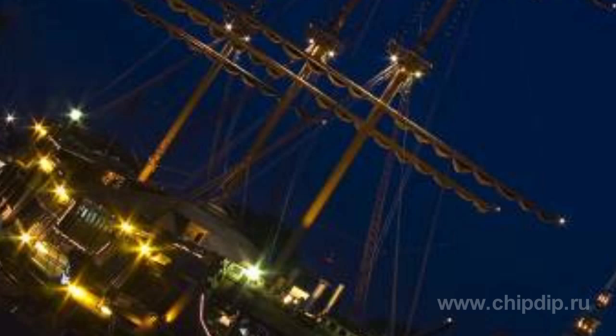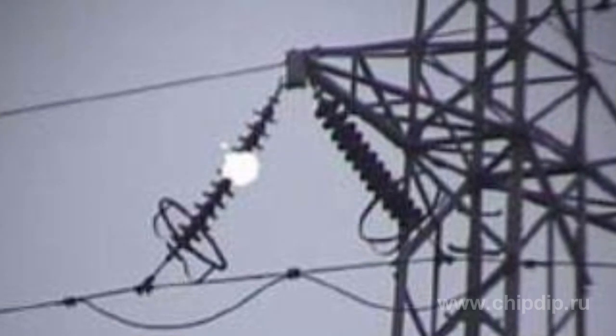Corona also occurs in nature under the influence of atmospheric electric field and appears at the tops of trees and ship masts. The possibility of corona discharge occurrence is always taken into account in high voltage engineering. A corona discharge affects the electric power lines negatively as it causes significant leakage currents. To avoid occurrence of corona discharge, the wires must have quite a big diameter. The diameter is greater for bigger voltages.